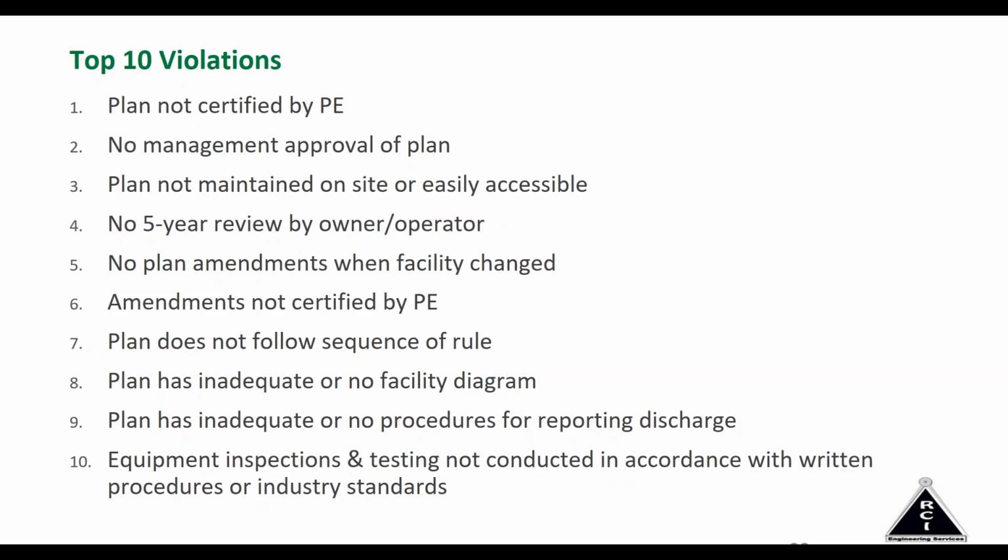Number 5, no amendments. If a plan is changed, you are supposed to list what the amendments were and when the amendments were made, and that is a section in the SPCC plan. The amendments may have to be certified by a PE depending on what they are. If there's any change in storage tank capacity, or your capacity to pollute, then anything having to do with that has to be recertified.